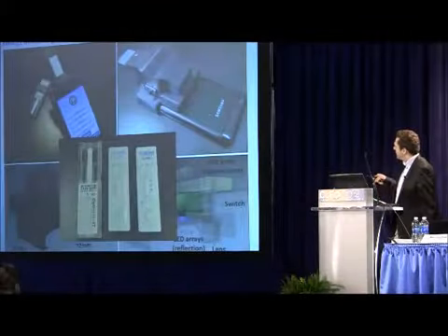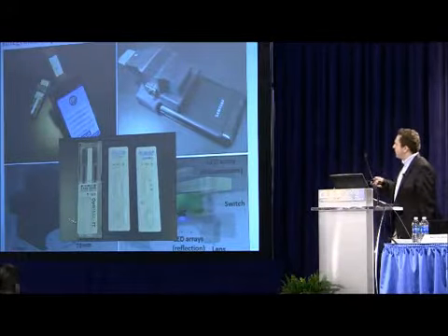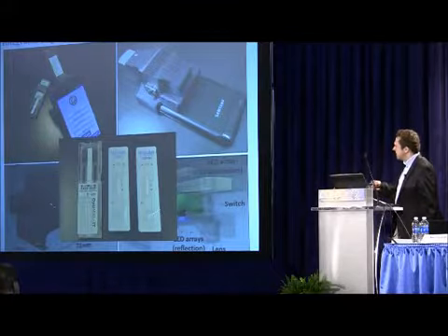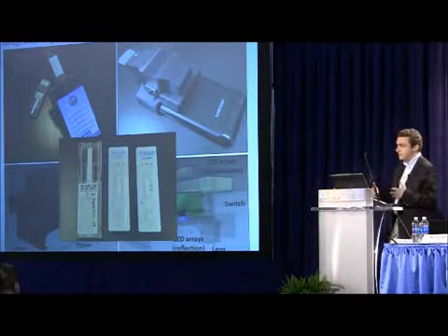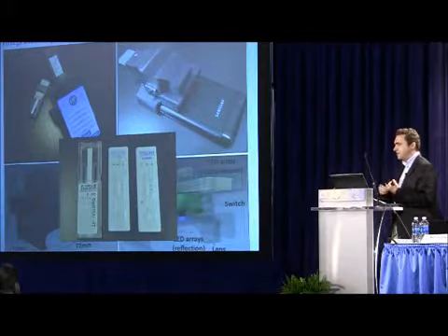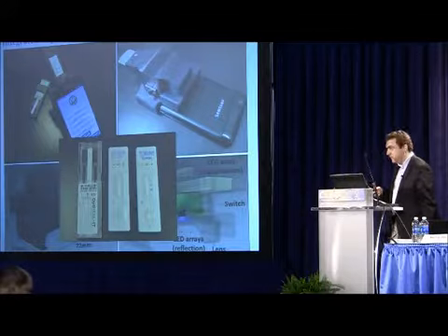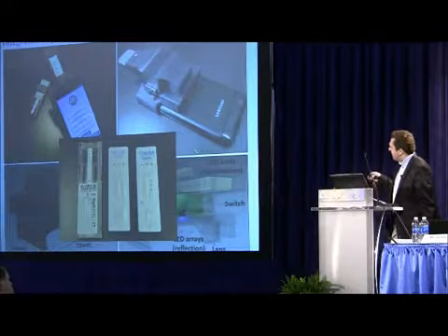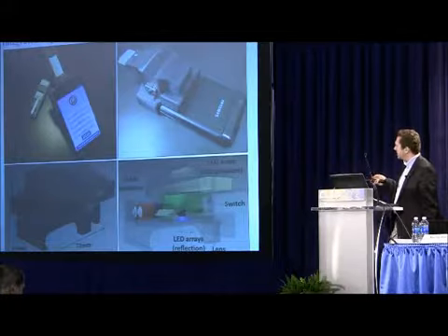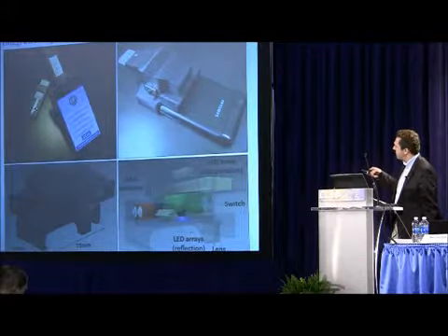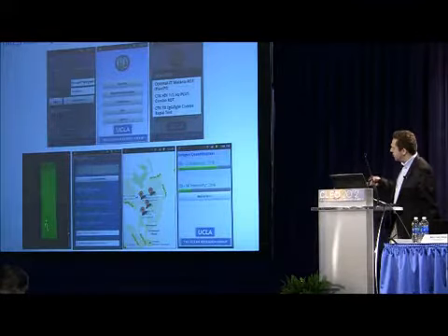In this case, we're looking at a digital reader for different rapid diagnostic tests. So rapid diagnostic tests, you can have literally several hundred different types of tests, whether it's an HIV test or sexually transmitted diseases or malaria or even TB. So we've created a platform which essentially can read any rapid diagnostic test universally using an attachment to the cell phone, and there's an application on the cell phone which essentially captures this image.